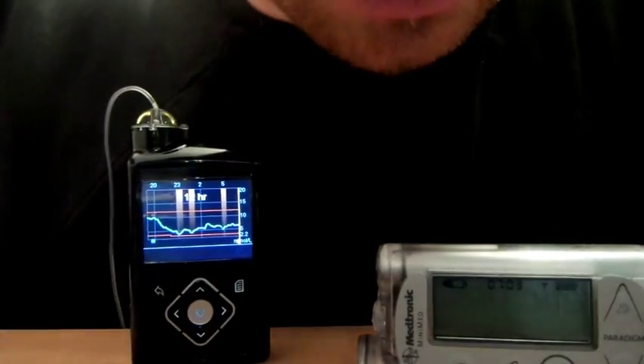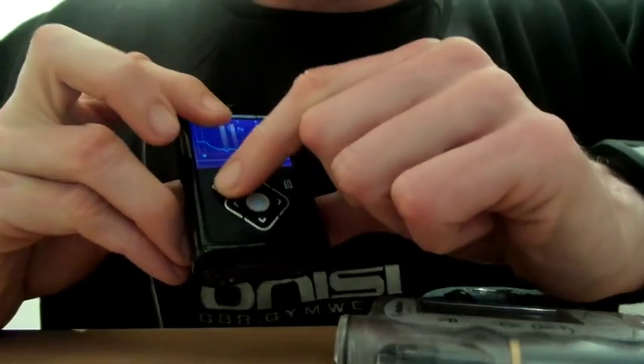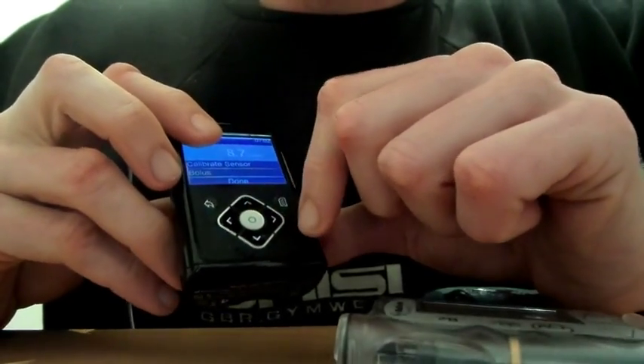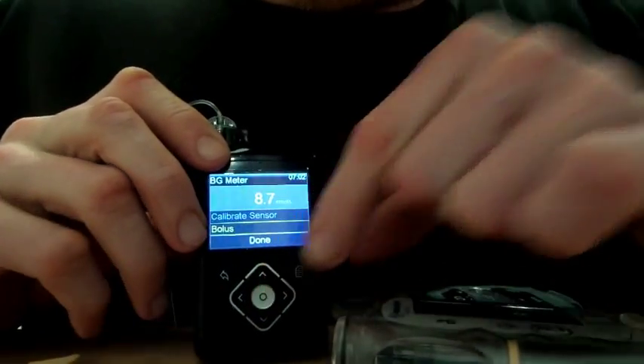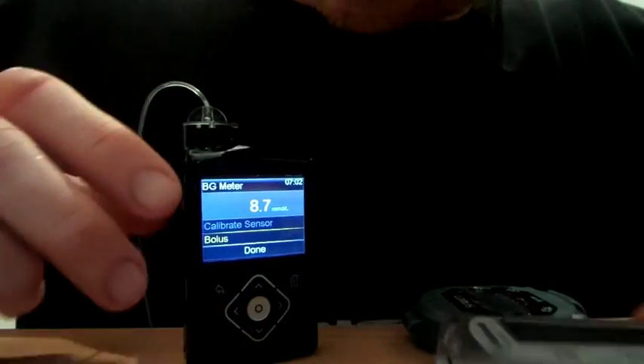Okay, 8.7. The values are a bit closer, however that's still not ideal for me. I'll calibrate the sensor and calibrate the values as well.